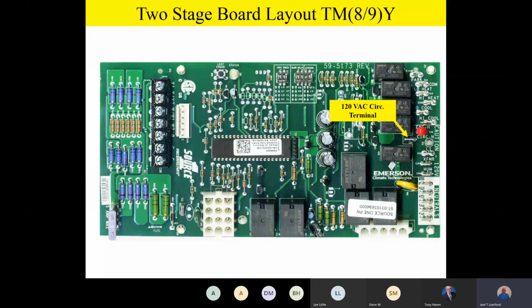The last board, we called it line. On this board, we call it circ. And so that's our high voltage going to the motor all the time to power it up. L1 is our 120 volt input to the board like we had before. XFMR is our transformer terminal just like we had before. And on this board, we also have a humidifier output of 120 volt called the HUM terminal.